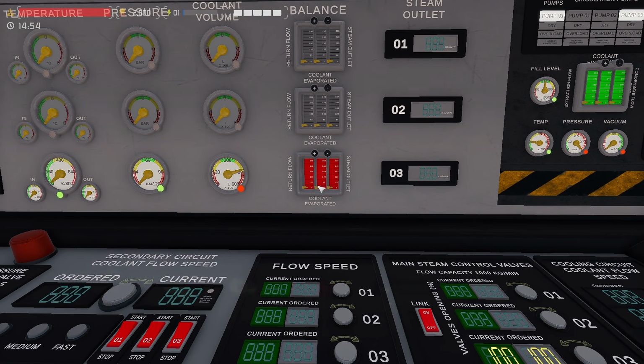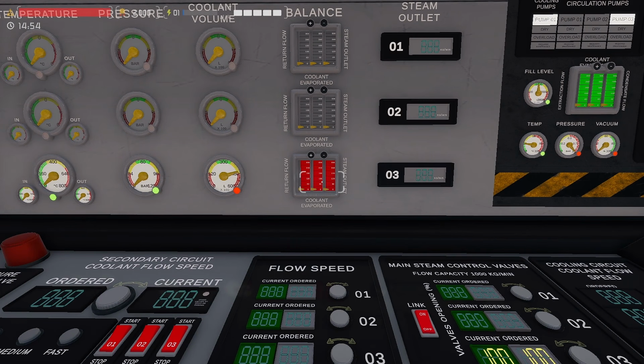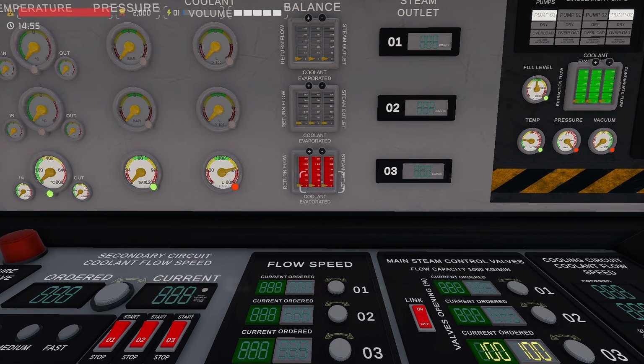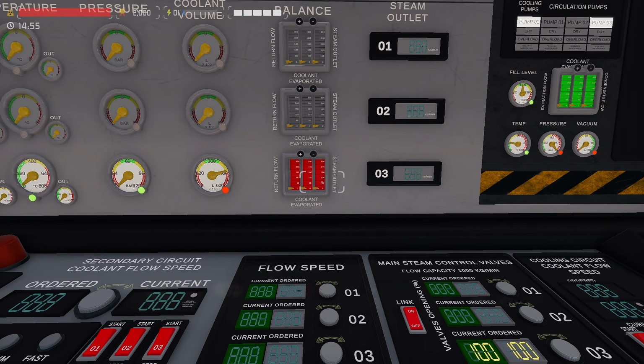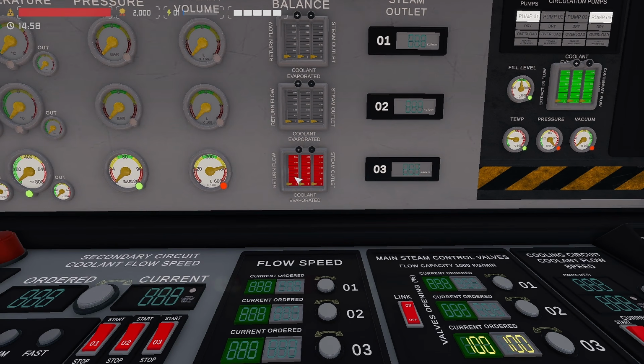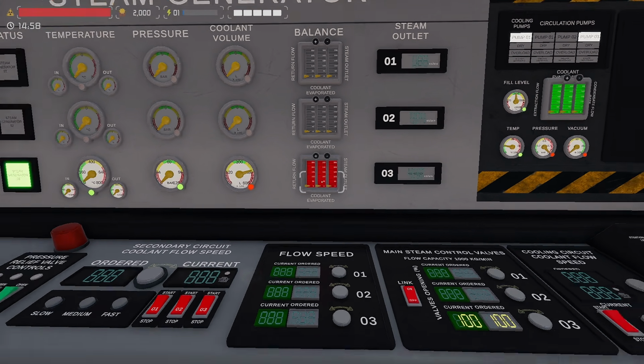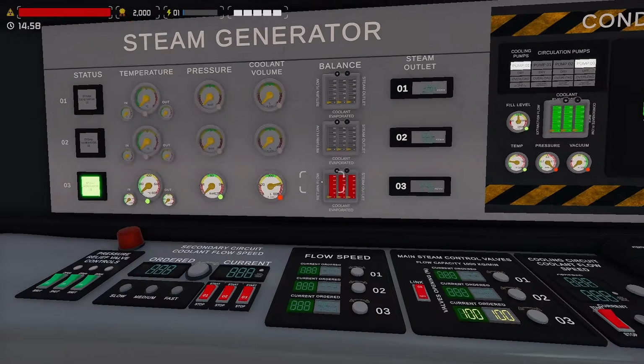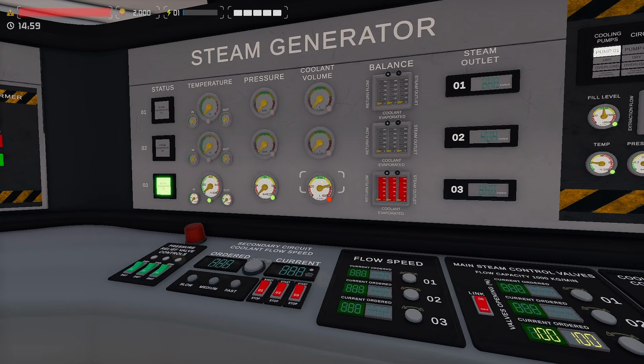The middle number is the coolant evaporated rate, how fast liquid water is turned to steam. The right number is how much of that steam is exiting the steam generator. When all three numbers are the same, you're in thermal balance: the water coming in matches the water turning to steam, which matches the steam exiting. When all three are in harmony, you have a constant system. For me this middle number bounces up and down a little, but in a system of 45,000 liters, 1, 2, 5, or 10 liters off is not bad.